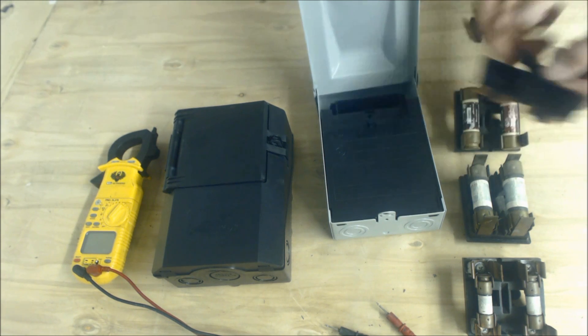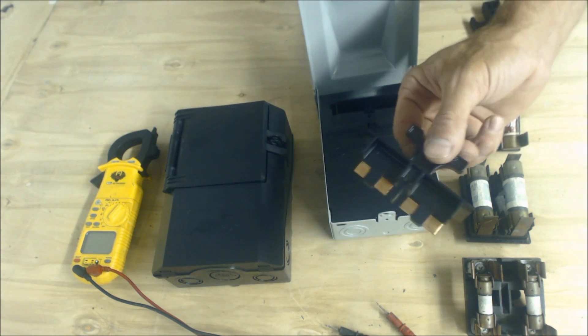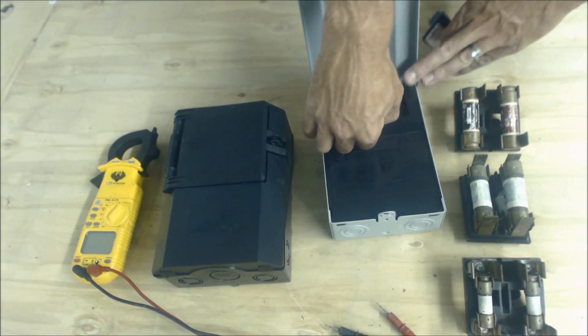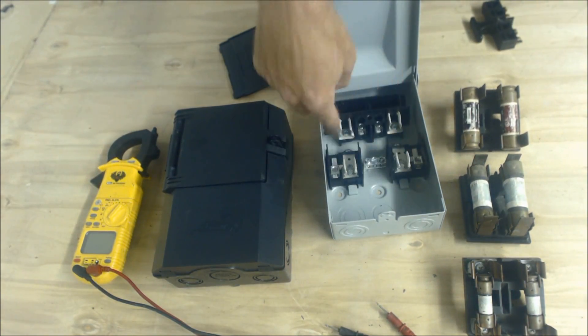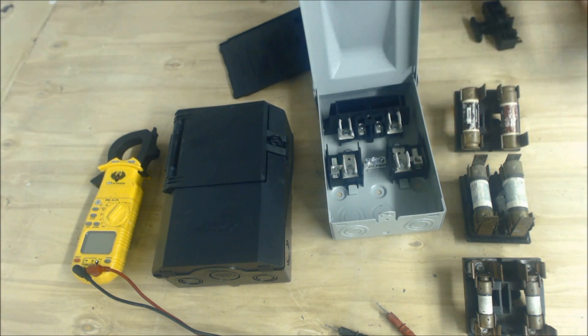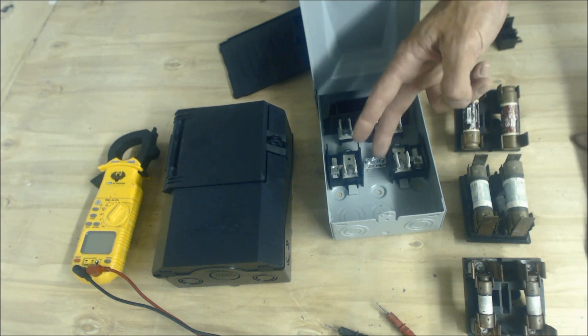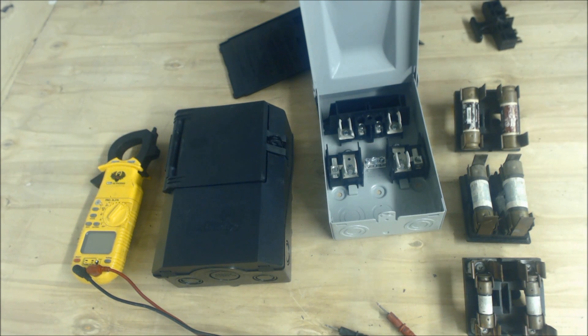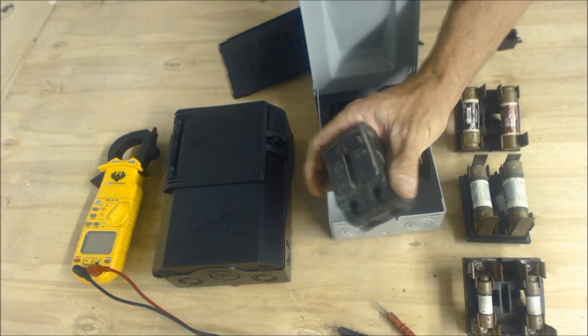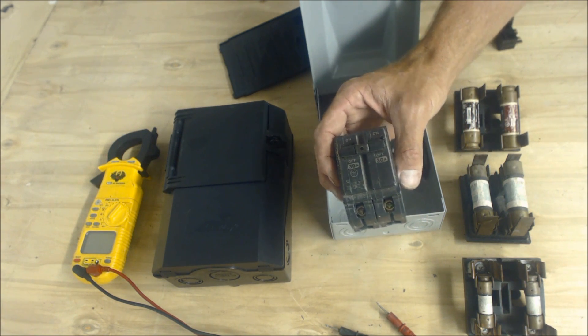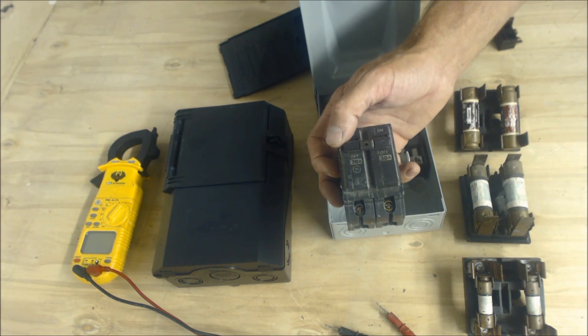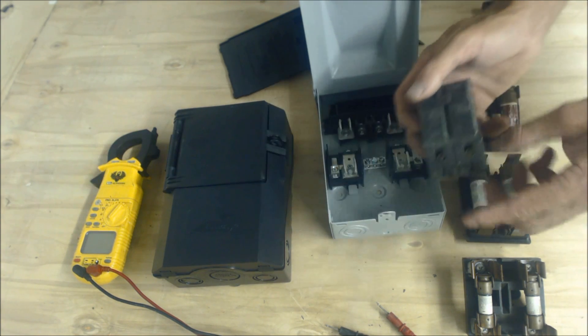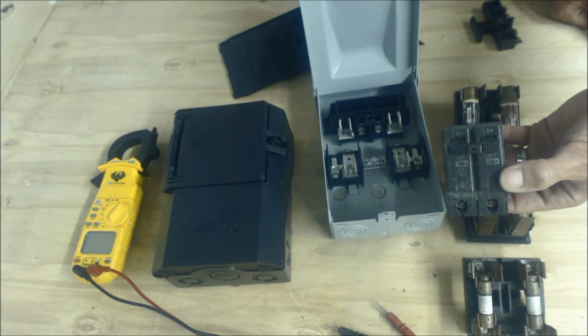So it's important to just slide this in partially and then tap it in to make sure you have a good electrical connection. The other thing is just because you have this does not mean that it's a non-fused disconnect. In this case, right here, there's a fusible portion right below. Now, the reason somebody may have installed a fusible disconnect is maybe somebody did a change out of an air conditioning system. Instead of lowering the breaker size due to the higher SEER ratings of the outdoor condensers or heat pumps, or maybe even a geothermal unit, instead of reducing the breaker size, what they've done is they fused it down outside.